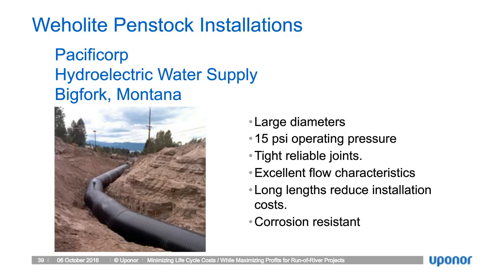And Black and Veatch were the designers. There's a typo there. The actual operating pressure is up to 8 psi. Tight, reliable joints, excellent flow characteristics, long lengths reduce the installation time, and very corrosion resistant. It actually replaced a wooden stave on this project.